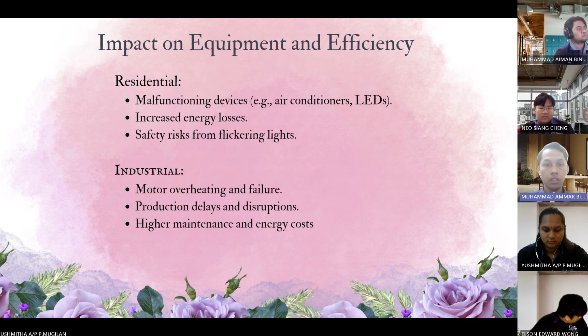For the case study, a manufacturing plant in Johor. The problems are motor failures, fluctuating light, and production interruption. The causes are unbalanced load on the three-phase system, supply fluctuation from a nearby solar farm, and aging transformer and distribution line. The solutions implemented are load redistribution for better phase balance, voltage regulator to stabilize supply, and infrastructure upgrades and preventive maintenance. The result is an 85% reduction in motor failure and a 30% improvement in production efficiency. Next, I will pass the presentation on.